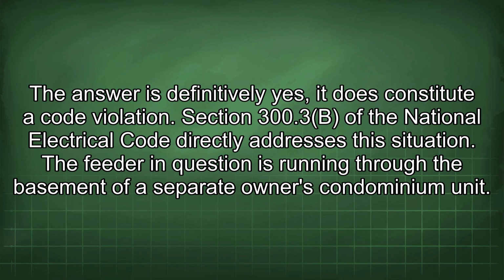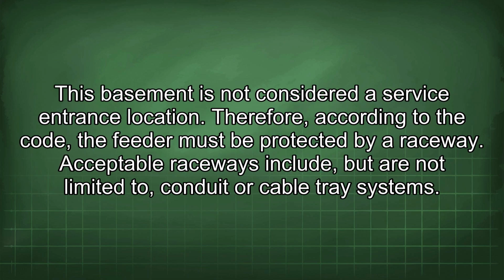Section 300.3b of the National Electrical Code directly addresses this situation. The feeder in question is running through the basement of a separate owner's condominium unit. This basement is not considered a service entrance location. Therefore, according to the code, the feeder must be protected by a raceway. Acceptable raceways include, but are not limited to, conduit or cable tray systems.